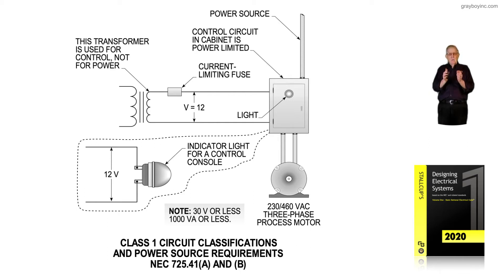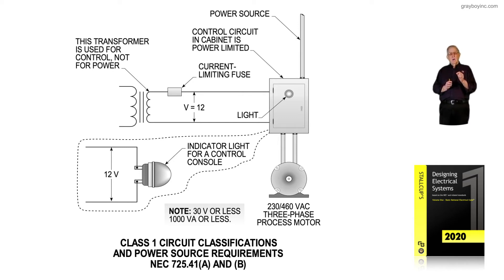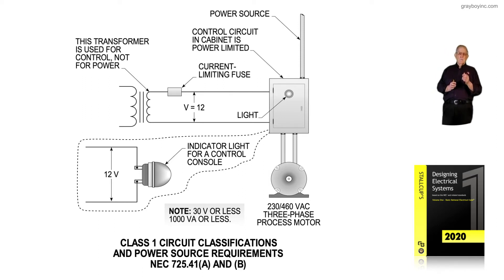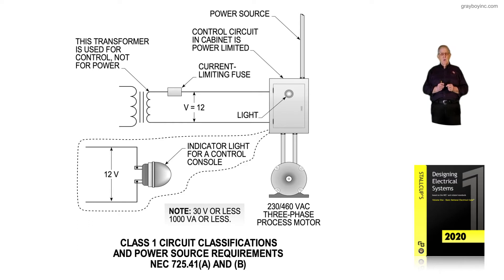If we had 240-volt three-phase feeding a contactor, we could take 240-volt control, or we could have 120-volt control. If you had 480-volt control, you could even take 480-volt control stop and start stations, giving you 277 volts to ground.